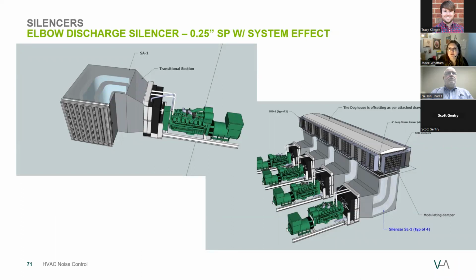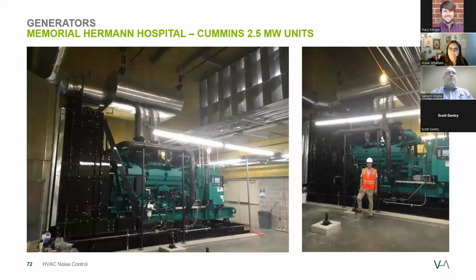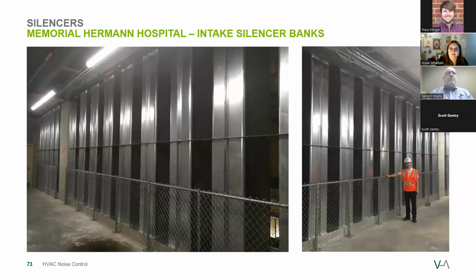These are some sketches of solutions for this project. Elbow silencers were used at the generator discharge and incorporated a doghouse with louvers once the air reached the exterior. It was designed to produce only 0.25 inches of static pressure, including system effects. In this photo, there's a human for scale to show the size of these generators. And then here's a few photos from the intermediate floor of the large bank of discharge elbow silencers. Above this was the doghouse with louvers we saw in the sketch a few slides ago.